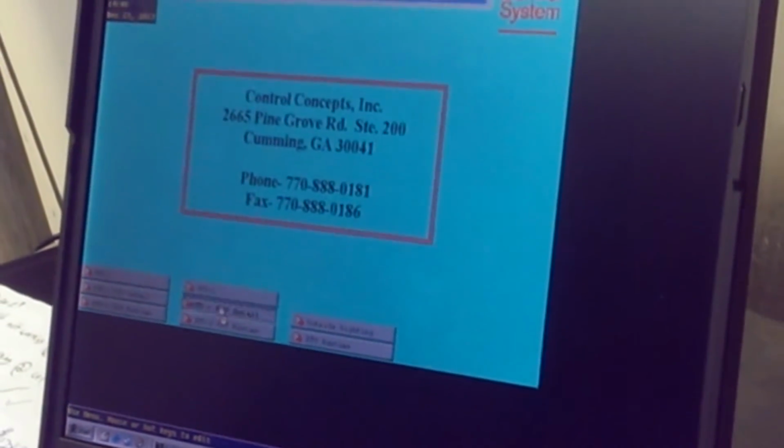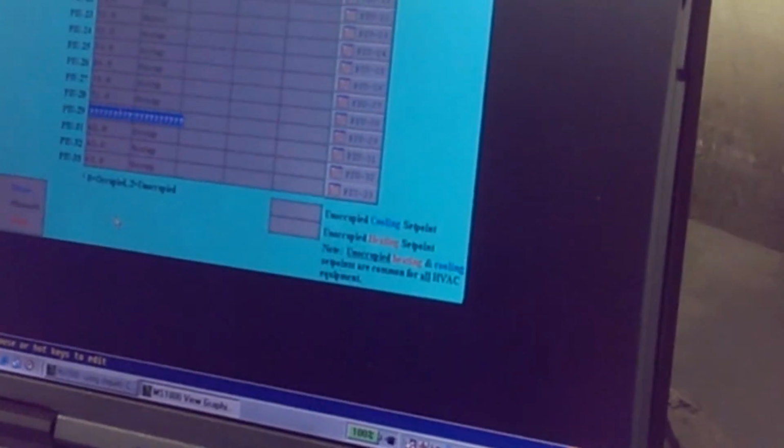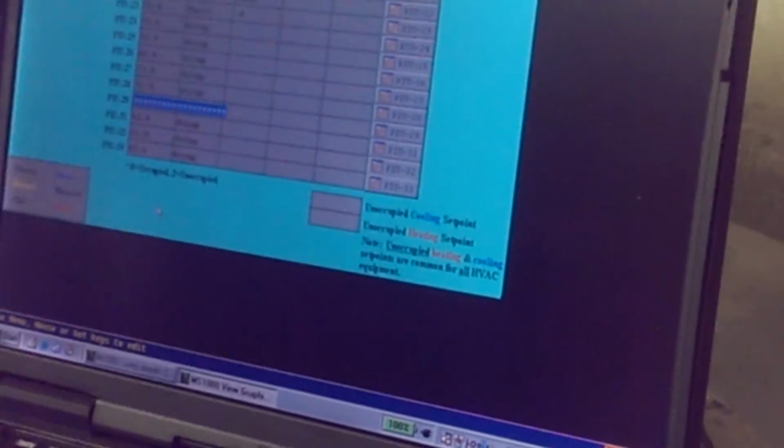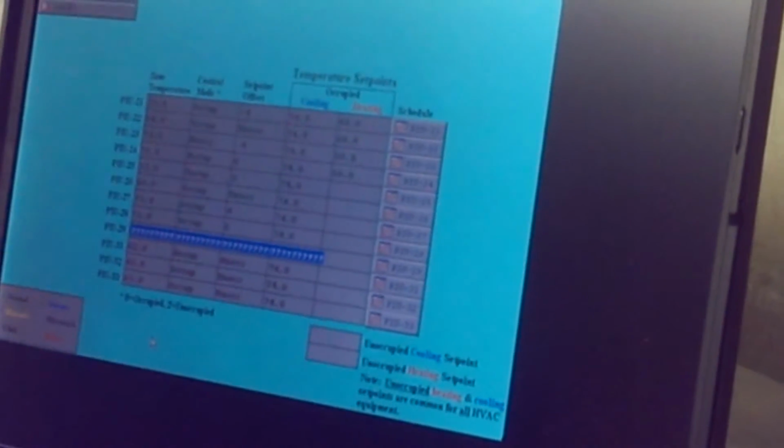All right. So if we go back and look, I'll go back to where we were just in. Let everything load up. You should see everything at 74 and 68, with the exception of the values that we're not talking to. You're not going to see those guys. So we need to go dig into those and find out what's happening with those units. You may find that the power's turned off. Maybe it's a common power source, that breaker panel's turned off, those breakers are turned off. Maybe the wire's cut, if they really do exist out there. The best thing to do is go look for those units, see if they've got power first of all, then backtrack from there.